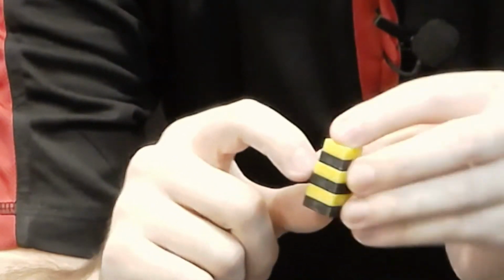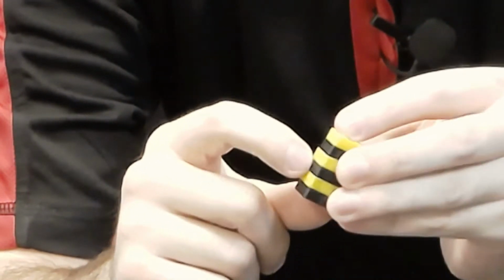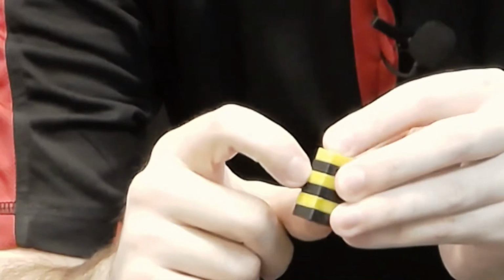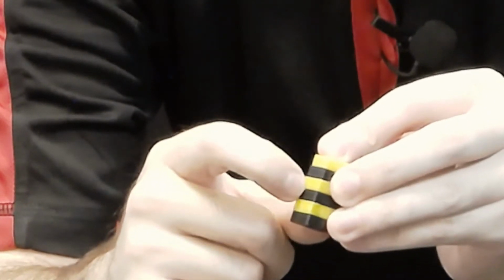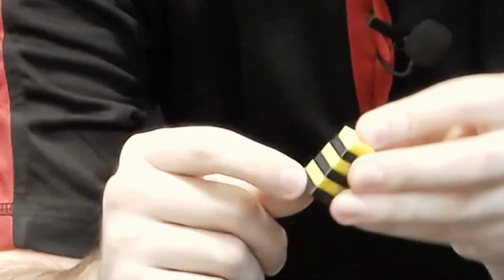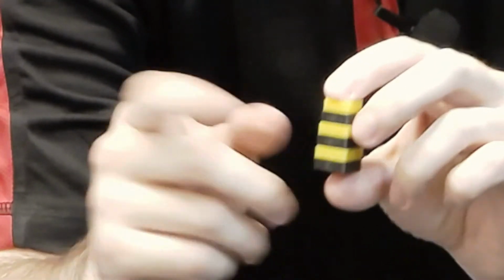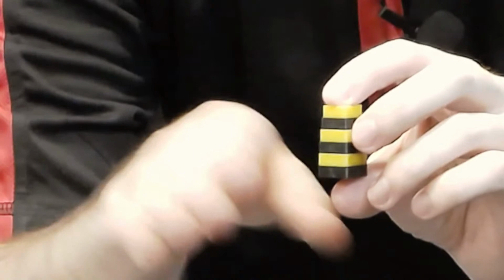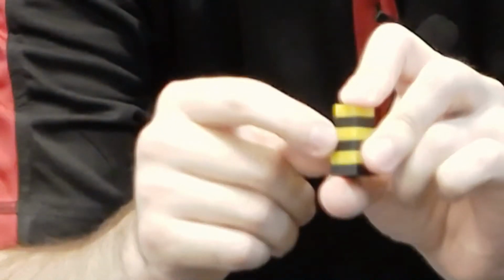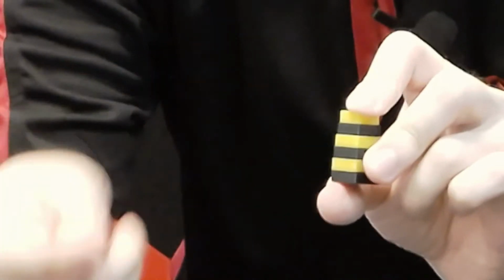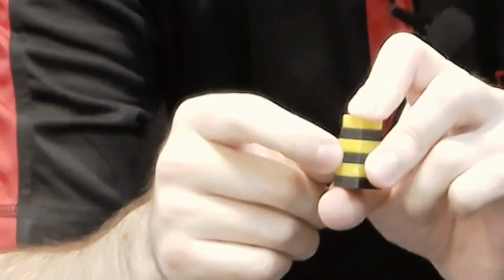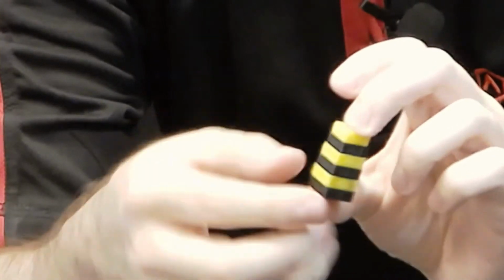So I'm looking at the two faces that are flush and then taking the value that is printed on the upper of the two flush faces. In this case, it's negative 0.3. That'll be in the X direction. So with the offsets already set to 25 and 0, 25 for X, you'll add this upper value to the existing offset. So we'll go from 25 in X to 24.7 millimeters for our corrected X offset.